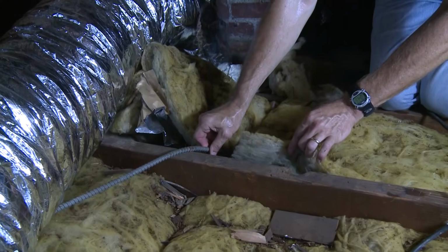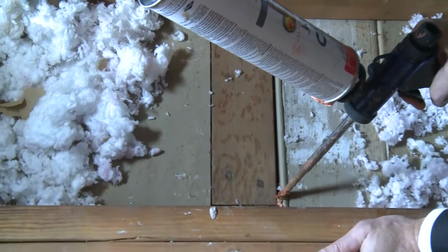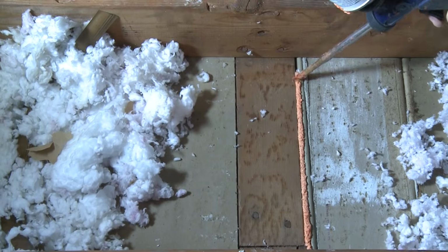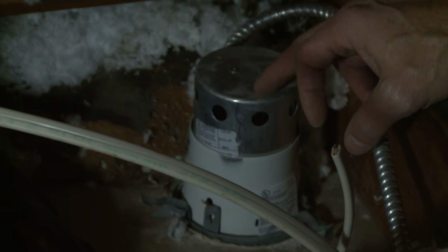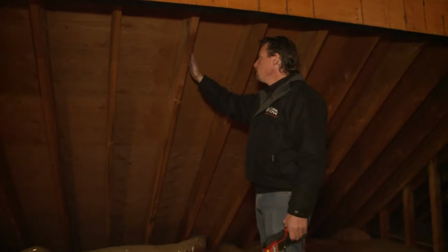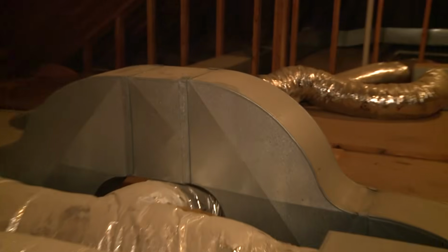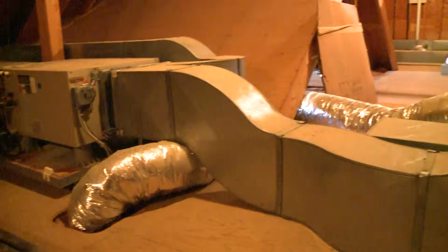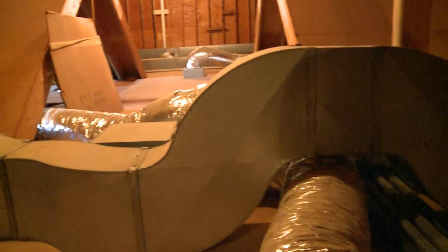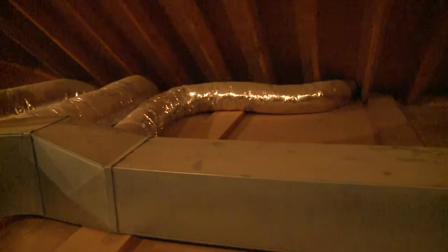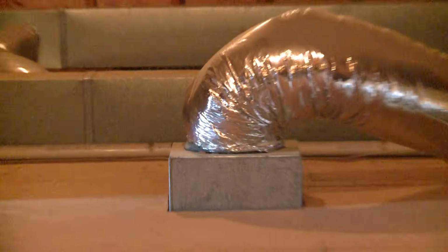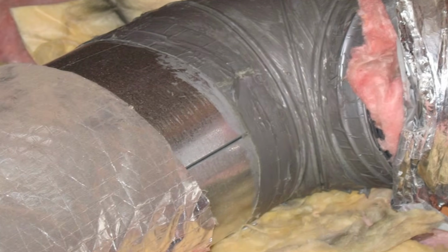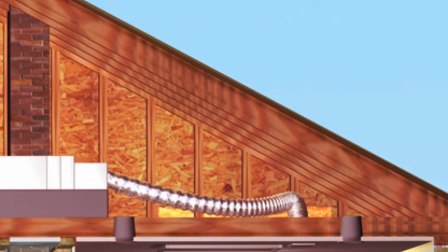It can get into the attic through pipe and wire holes, through the top of interior and exterior walls, around the chimney. Can lights are big leakers, and all kinds of framing details and plumbing and duct chases. And you also have ducts in an attic. That is a terrible thing because ducts leak and you're paying to heat the air. You're sending it through the ducts, and a percentage of the air that's in the ducts is leaking out of the little holes and gaps and seams and joints in that duct, and you're heating your attic by accident.